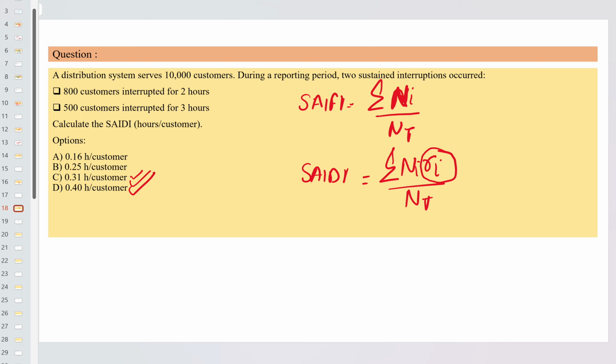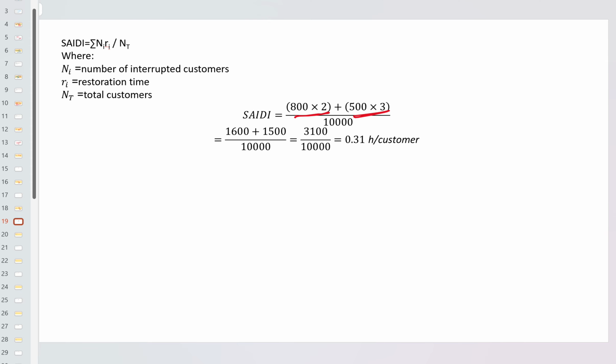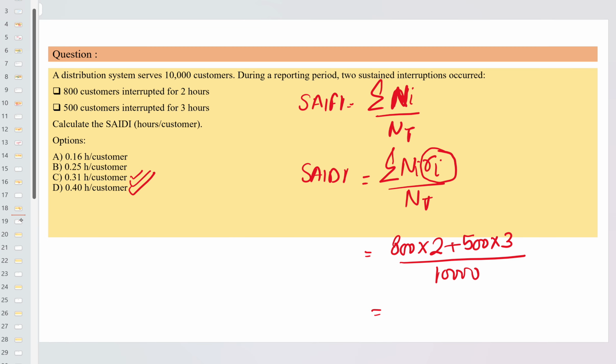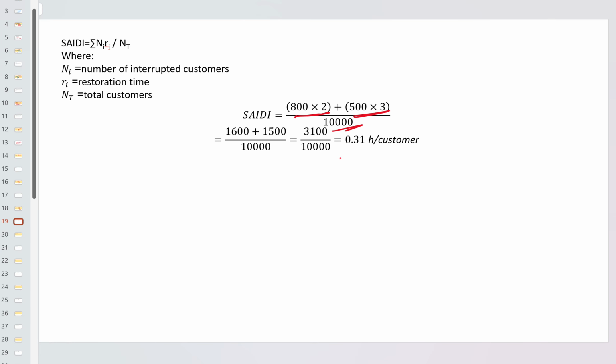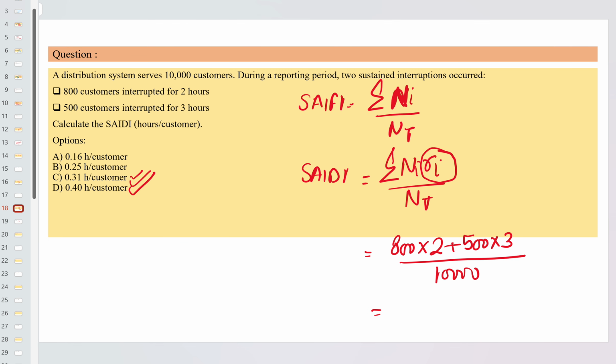So when you try to solve for SAIDI: 800 customers were interrupted for 2 hours plus 500 customers for 3 hours, and total 10,000 customers were there. So 800 multiplied by 2, plus 500 multiplied by 3, divided by 10,000. When you solve it, it comes out to be 0.31 hour per customer. Ri is the restoration time, Ni is the number of interrupted customers, Nt is the total customers.